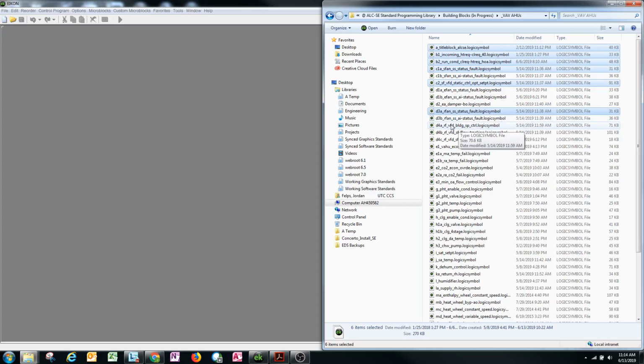We're not doing building static pressure control like I mentioned. We're not doing flow tracking because we don't have flow stations on the supply and return. So we'll just plan on doing speed tracking. Also, we got economizer options with mixed air temp, return air temp. We didn't have any CO2 overrides or return air CO2, so we'll leave that out.